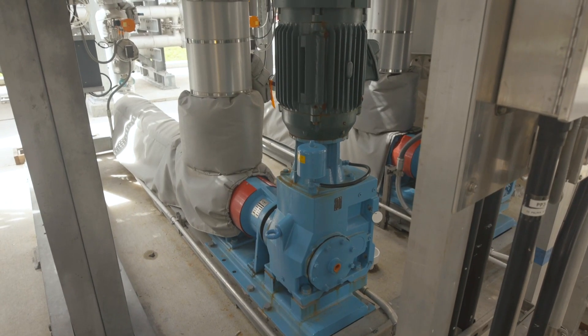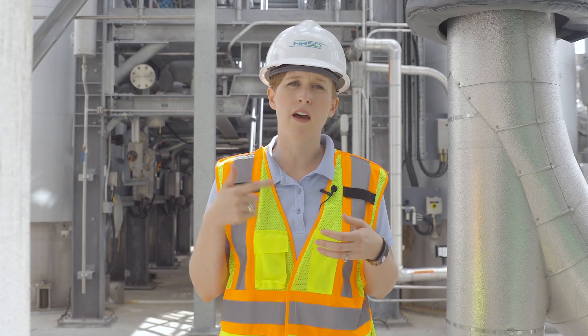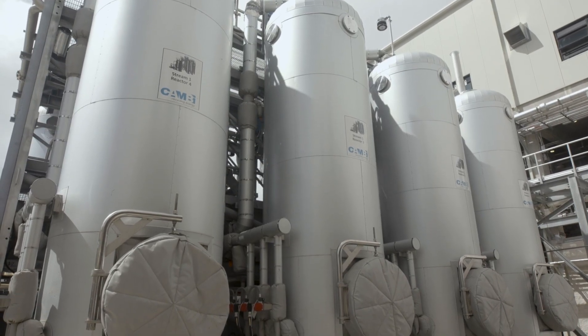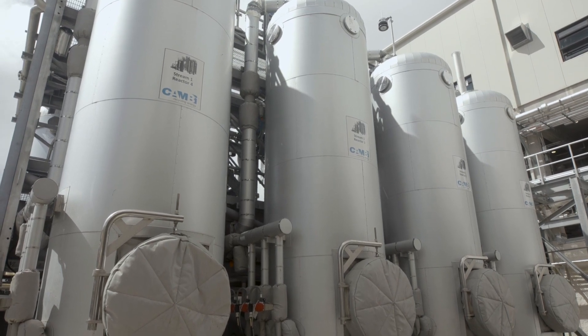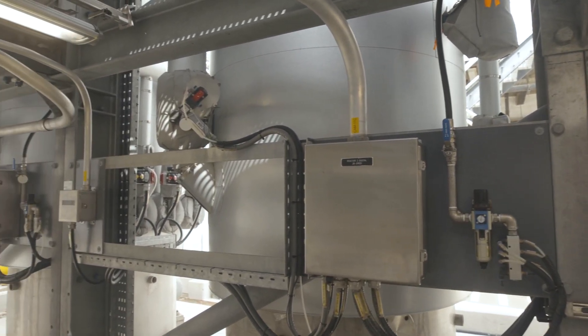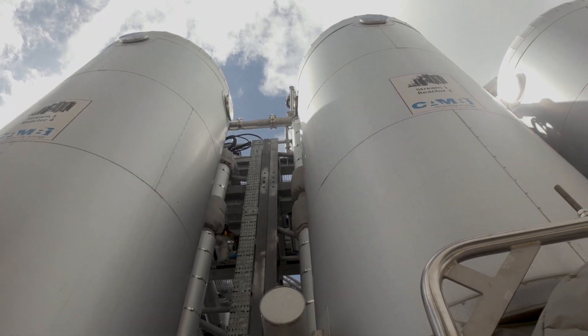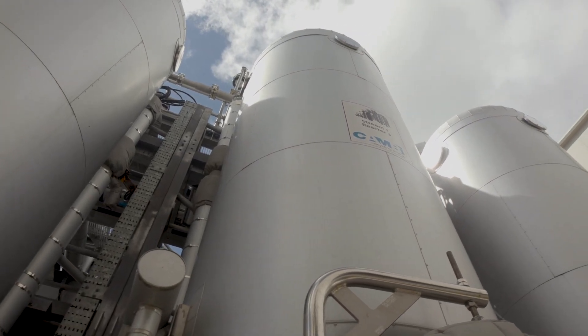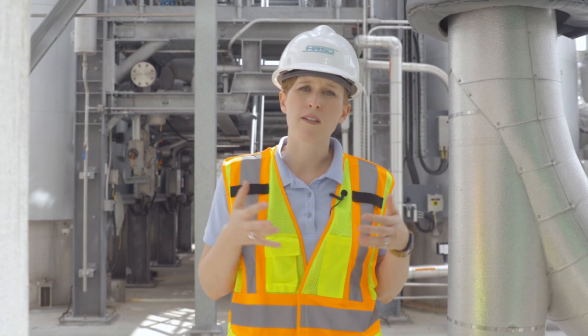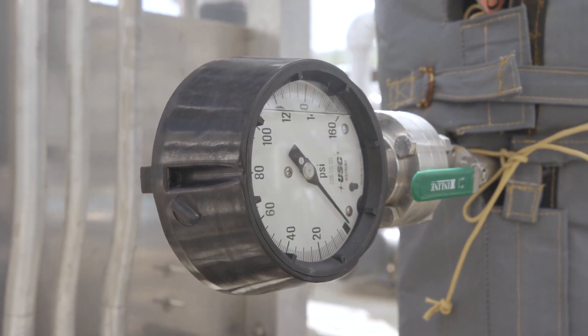After the pulper, we have two duty pumps that are either recirculating the solids in the pulper to help maintain efficient heating, or feeding the reactors. As I said, Cambi is a batch process — the reactors are fed, then brought up to temperature and pressure. We're holding about 87 psi, which is about 165 degrees Celsius within the reactor. We hold that temperature and pressure for about 20 to 30 minutes, and then we go to the flash tank where our blow-down process happens. That's really where the magic of thermal hydrolysis happens — we're disintegrating the cells when we go from this high pressure of 87 psi back down to about atmospheric pressure.